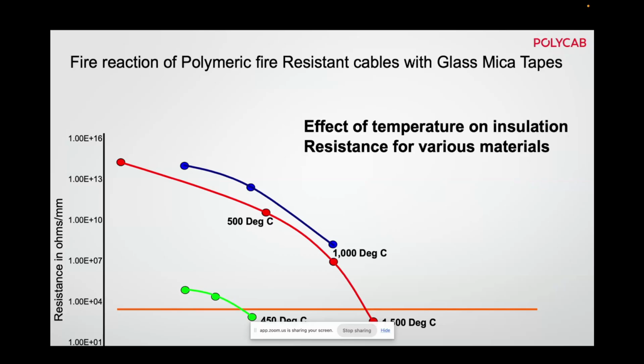Another is the insulation resistance at operating temperature. Normally the operating temperature of this kind of cable is 90 degrees, so we supply the insulation resistance data at 90 degrees. That will be around 1 into 10 to the power 10 or 10 to the power 11. But when the temperature goes very high, this insulation resistance falls down. If you see the green color, it is glass. The glass insulation resistance as such is not much, but when the temperature goes up, it goes below this line. This line is designed so that if something goes below it, that material becomes semiconductive. So glass becomes semiconductive at 450 degrees temperature.